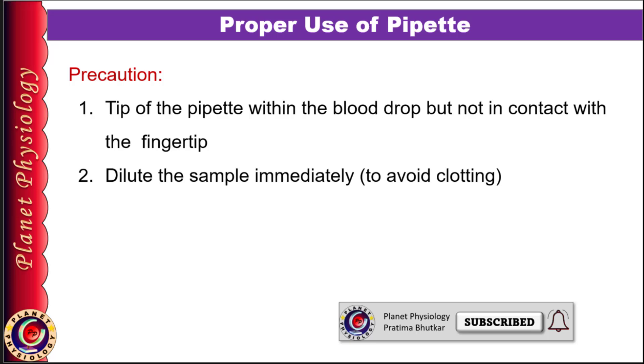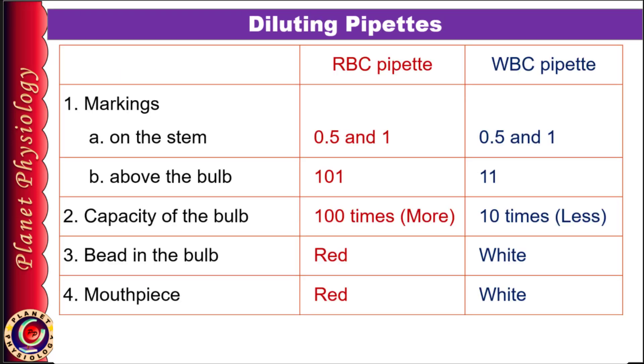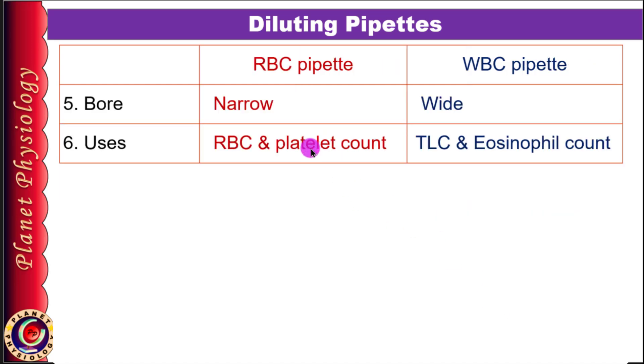Before winding up the session, let's go through the important points. Pipettes in the hemocytometer are used to dilute blood samples to facilitate cell counting. The RBC pipette has a larger bulb and a 101 marking above the bulb, while the WBC pipette has a smaller bulb and an 11 marking above the bulb. The RBC pipette has a red bead and red mouthpiece, whereas the WBC pipette has a white bead and white mouthpiece within the bulb. The RBC pipette has a narrow bore and the WBC pipette has a wider bore. The RBC pipette is used for RBC count as well as platelet count, while the WBC pipette is used for total WBC count and eosinophil count.